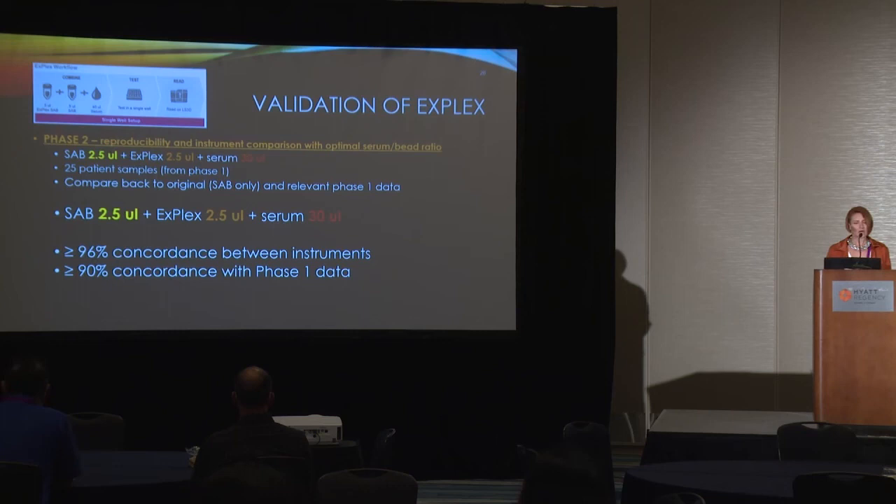For Phase 2, we performed a reproducibility and instrument comparison test with the chosen optimal serum-bead ratio. We ran as many remaining samples from Phase 1 as possible on three Luminex 3D instruments in the lab, showing 96% concordance between instruments and about 90% concordance with the Phase 1 data. We approved the validation in December 2020 and immediately went live. Since then, we've performed a little over 9,000 antibody identification tests with ExPlex beads.